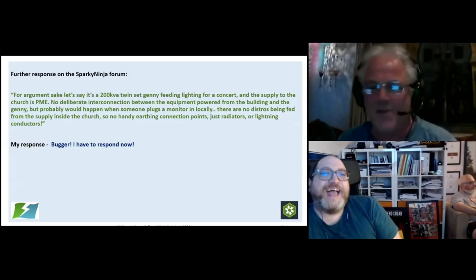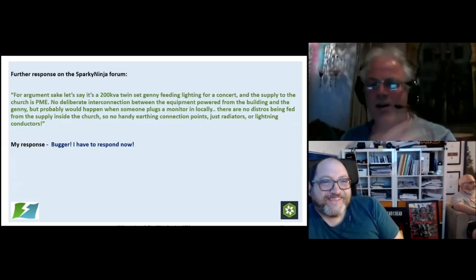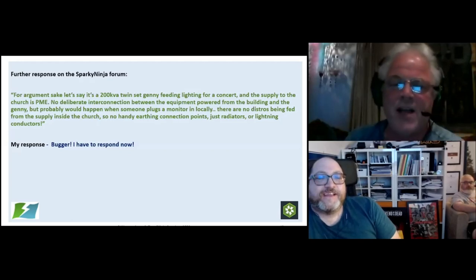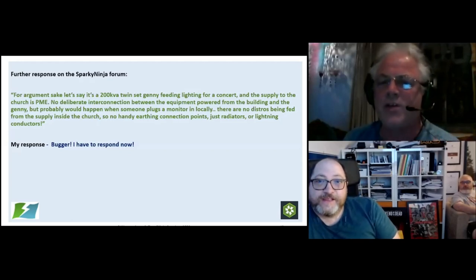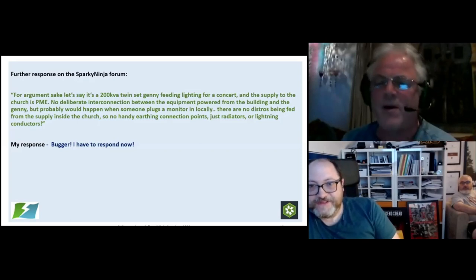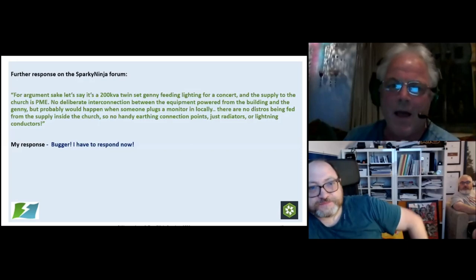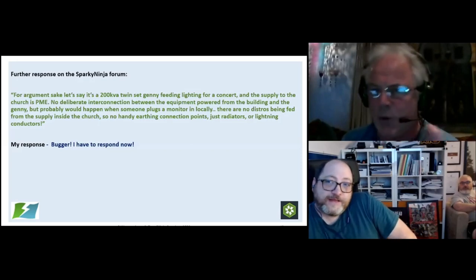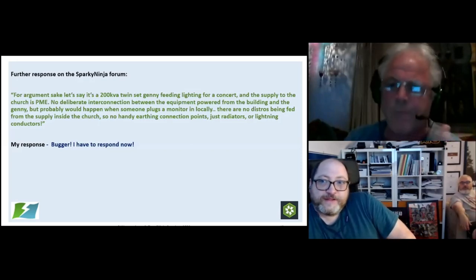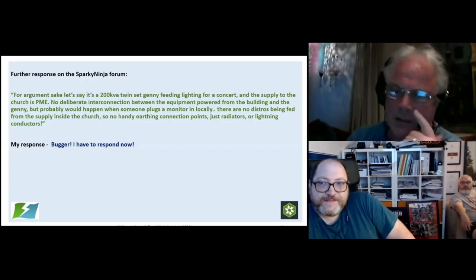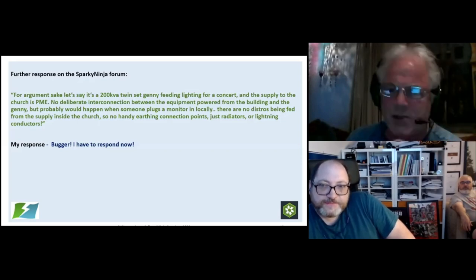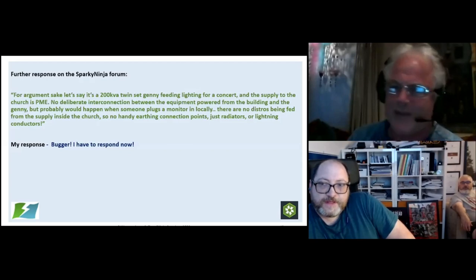and this is a further response, yeah? The guy asked a specific question about a 200 kVA twin genny set feeding lighting for a concert, which is actually inside a church, which has got a fixed installation fed by a PME system. Okay. And you've actually mentioned a book that was written by a guy that we both know, where he suggested connecting other conductive parts. Okay, and the chap mentioned what connects onto a radiator. I totally agree with his sarcasm there.